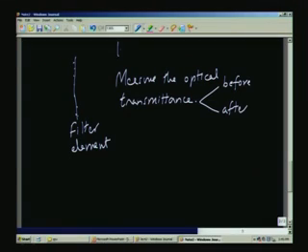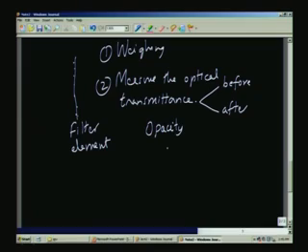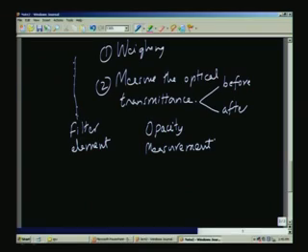So, this is second way of doing it. One is already I said weighing, first one. Second one is measuring the optical transmittance of the filter element. So, this measurement is also actually called opacity measurement. So, what we will do is, opacity measurement can be done in this case also, but what I will do is I will describe an opacity measurement in the in situ case, because there we are not collecting the material.